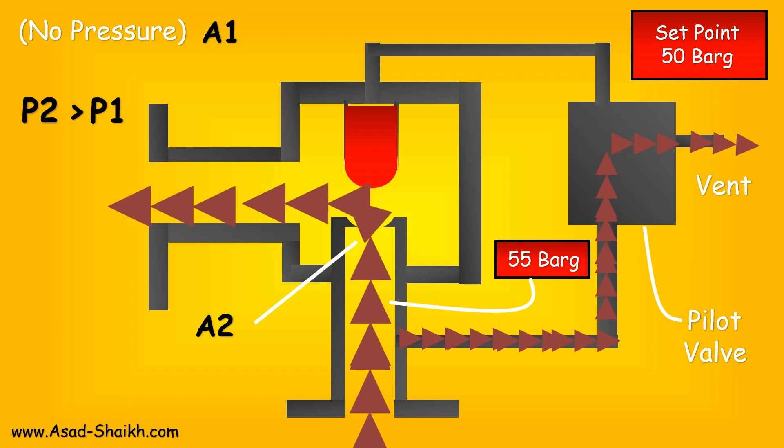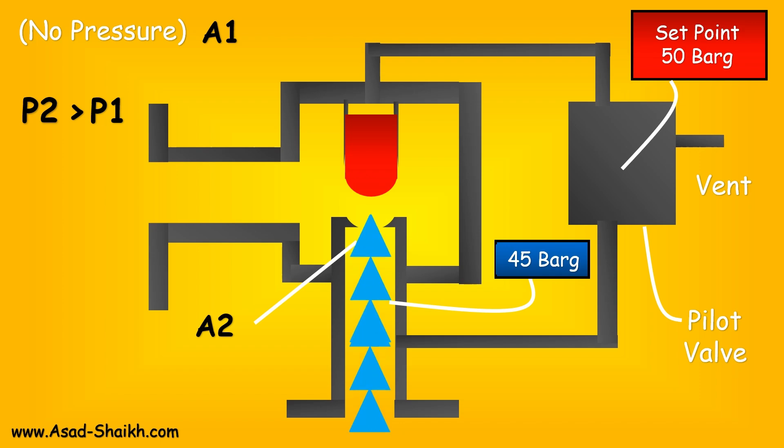Please note that this entire phenomenon is happening in just a few milliseconds. As soon as this pressure is getting released, eventually the inlet pressure is going to get reduced. If you see here, this pressure has now gone to 45 bar. When that happens, this pressure is also getting translated at the same time to your pilot, but the pilot is set at 50 bar.